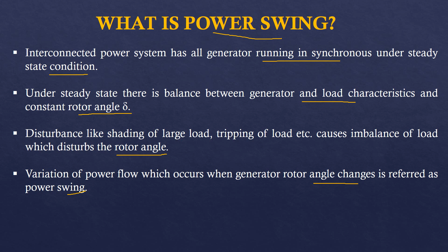Also, we know that the power flow through the transmission line depends upon the voltage generated at both ends of the line, and the phase difference between the two voltages is proportional to the rotor angle. Since this rotor angle is changing, the phase difference also keeps on changing. As a result, the change of impedance in the transmission line occurs, and therefore power swing also affects the distance relay scheme applied in the system. Therefore, the power swing becomes a need of concern.